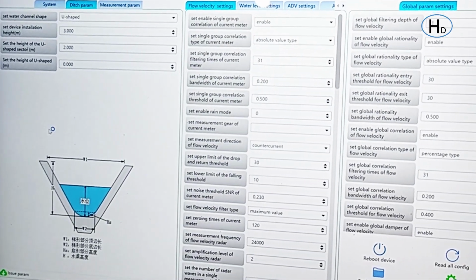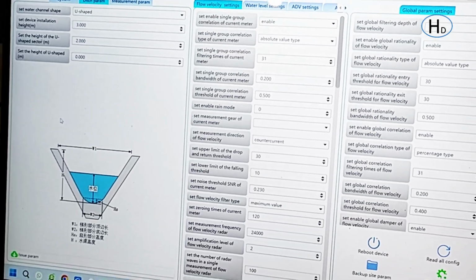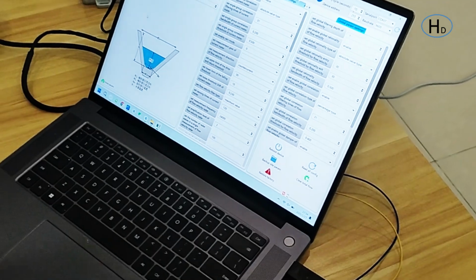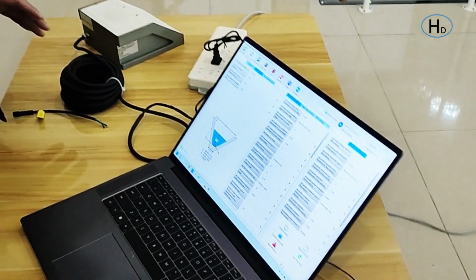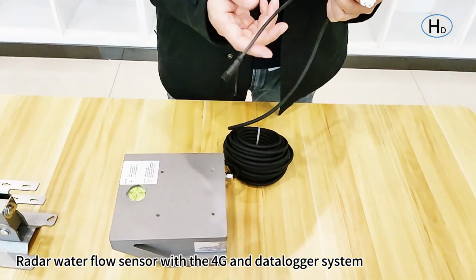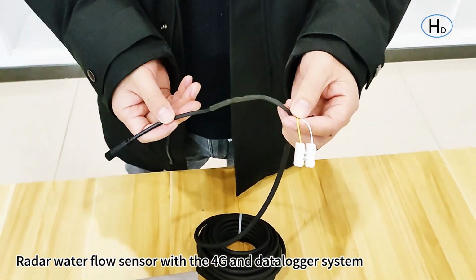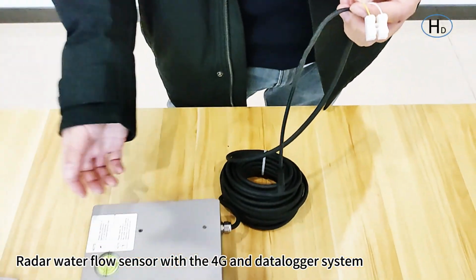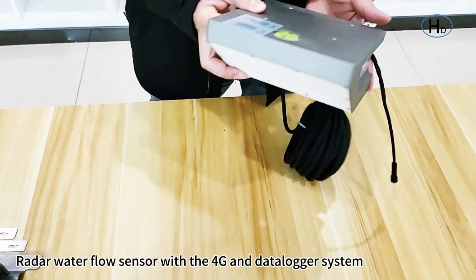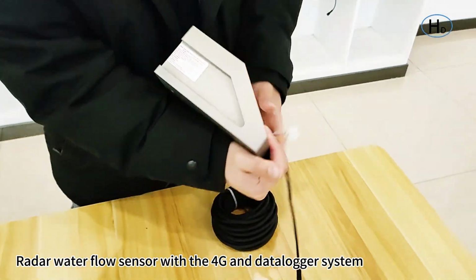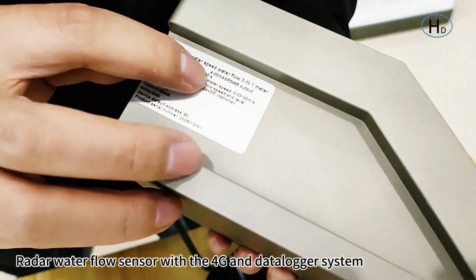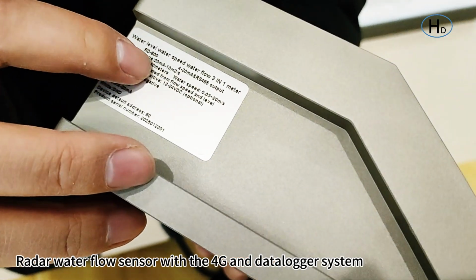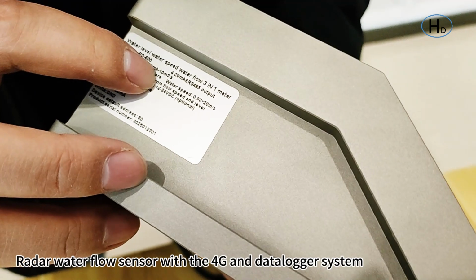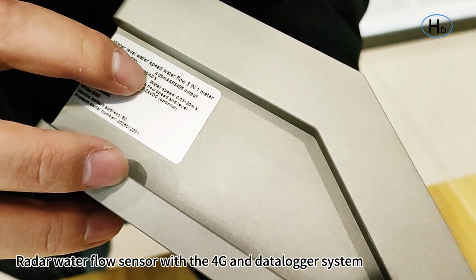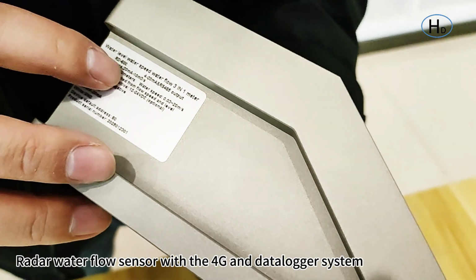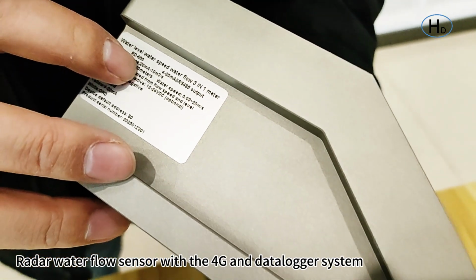Okay, and that is the basic introduction of the radar sensor. And next, I will introduce how to connect the wireless module. Okay, thank you. This sensor has an RS485 output, and also here is a 4-20 mA output. We have marked the two tabs here, and you can check it. For this 4-20 mA output, 20 mA corresponds to 10 cubic meters per second. So we have marked here, and you need to pay attention to that.